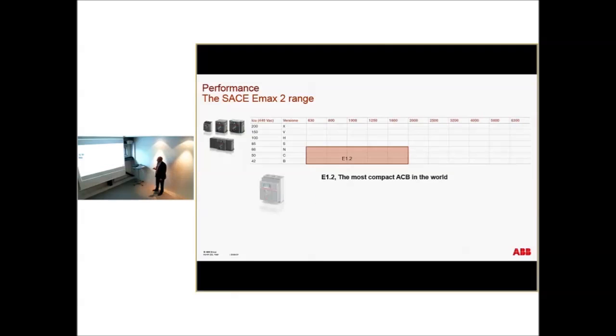Let's start from the smallest. It's the most compact ACB in the world. You have Icu that goes up to 66 kA or 50 kA at 690 volts. Withstand breaking capacity, which is important for discrimination, goes up to 50 kA for 1 second. 20,000 mechanical operations. Why do we list that? Because even if it's smaller, the operation is exactly the same as a big breaker.